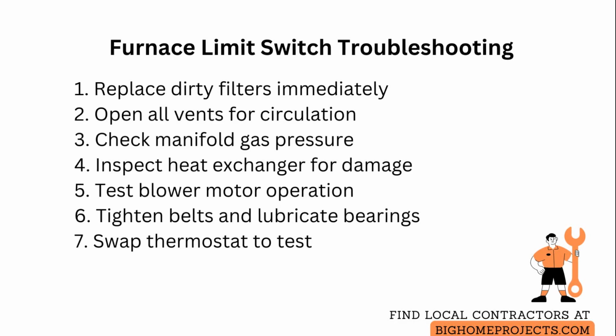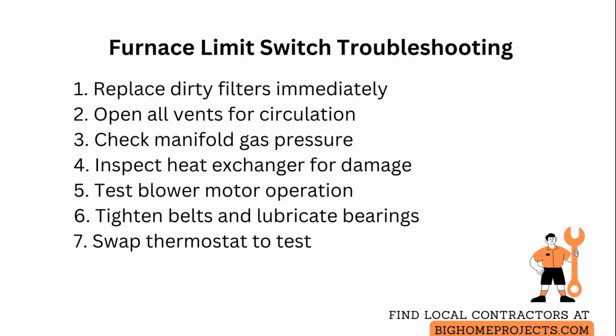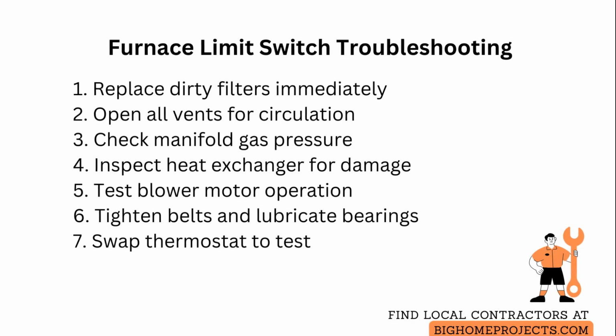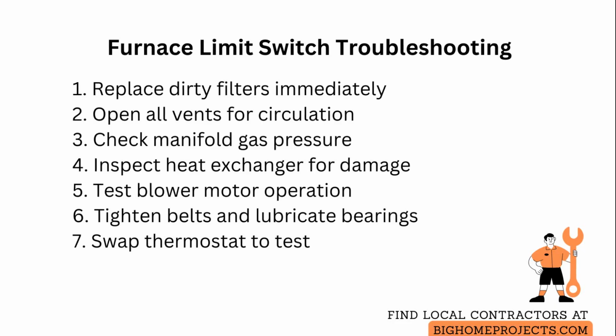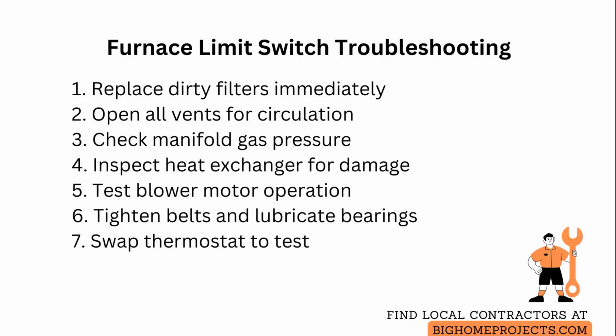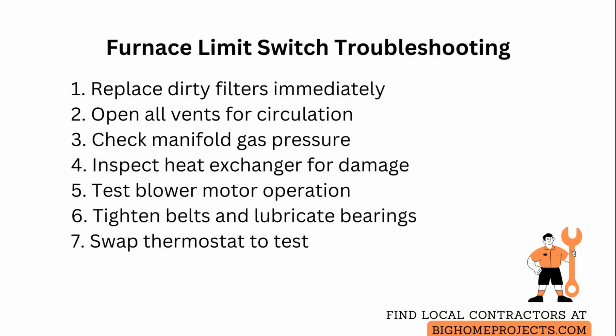High gas pressure or incorrect burner adjustment can drive temperatures above safe limits, so have a qualified technician measure manifold pressure and adjust the gas valve to manufacturer specifications. A cracked or partially blocked heat exchanger can create hot spots and poor heat transfer, and if you suspect this, inspect for rust or soot and arrange immediate repair or replacement because that damage can worsen quickly.